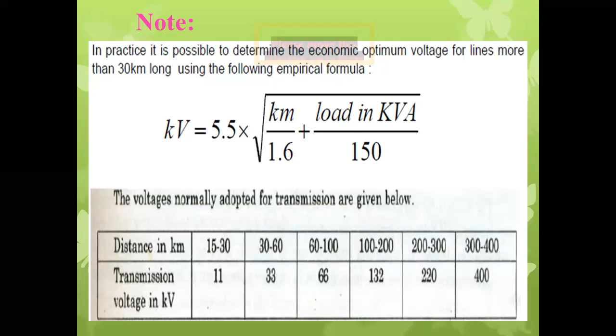Indirectly, if we know the length of the transmission line and the apparent power or total power to be transmitted to the load, we can directly find what voltage level should be achieved at the transmission substation in order to transmit the electrical power up to the load end. So remember this formula. It is an empirical formula, so it can be used all over the world. Once we know the total power to be transmitted and the length of the transmission line in kilometer, we can use it. If the length is in meter or miles, we can convert it into kilometer. 1.6 kilometer is nothing but 1 mile.